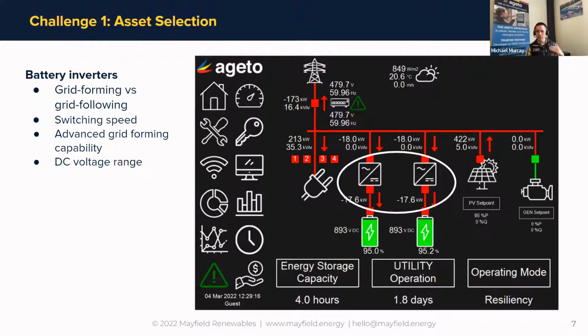At the bottom, you have the basic inverters, which can only operate in grid following mode, similar to a PV inverter. But for some applications that's great - if you're just doing utility rate optimization or energy shifting, you don't need a grid forming backup resilient power system, so that might be all you need and you can save some money. Other inverters can actually switch from grid following to grid forming in milliseconds, so if there's a utility outage, the entire facility can have backup power seamlessly and won't even notice the lights flickered. Other inverters can switch modes too, but it might take over a minute to start up in grid forming mode. So depending on what you need and what the facility requirements are, there's a wide range of inverter selections.